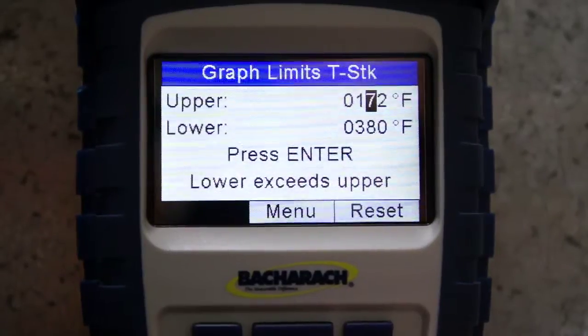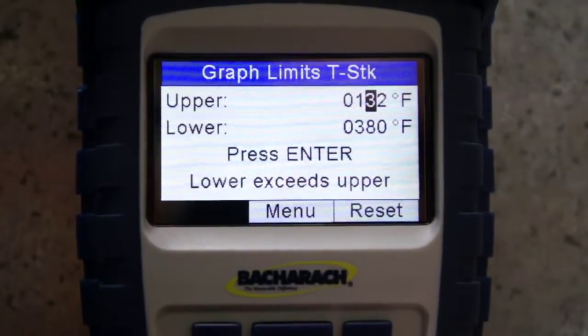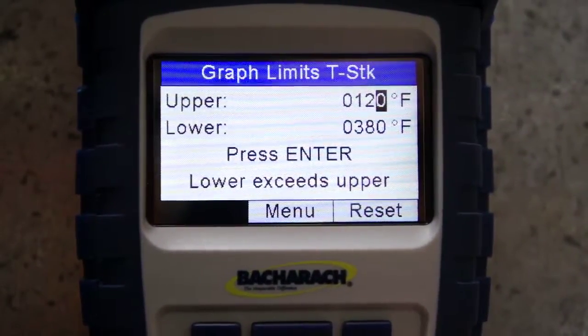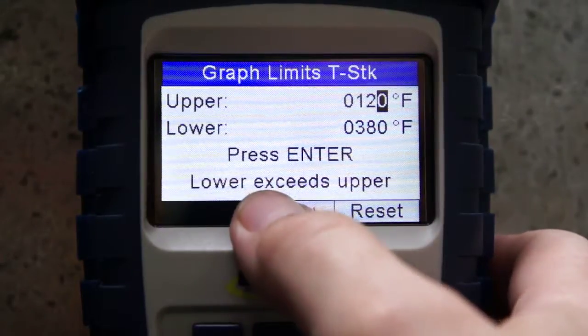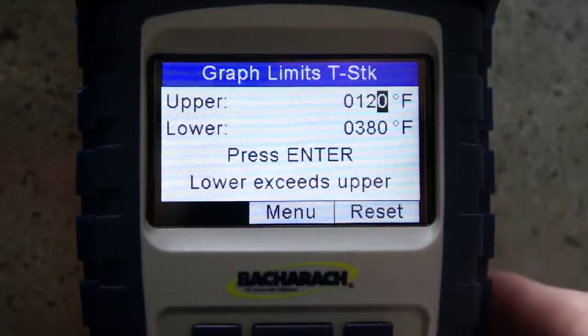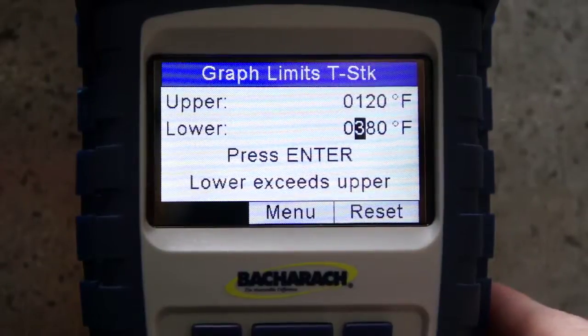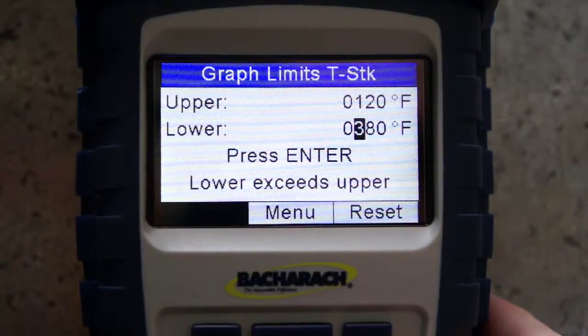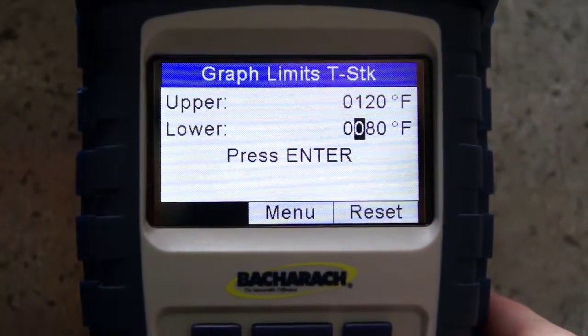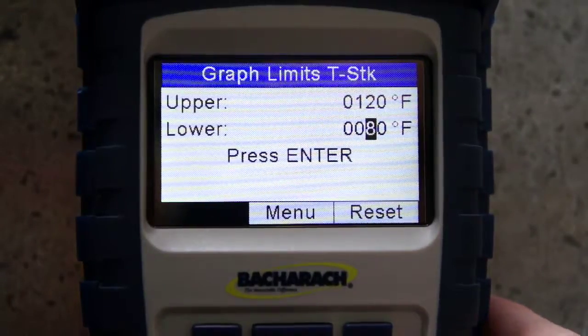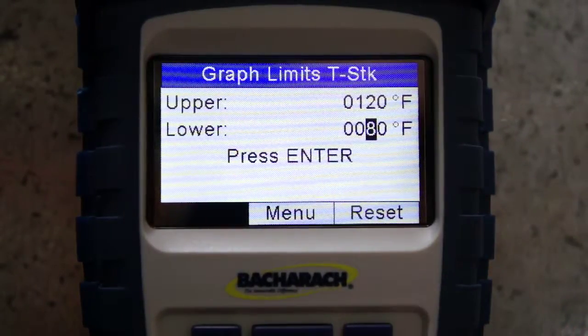Oops, we'll go back up to 1, 2, and 0. And you can see how I have a lower limit exceeds upper, so I definitely have to change the lower limit. My lower limit really should be my return air temperature and no lower than that. So I'm going to go to 80 degrees. And maybe I'll leave that, 80 is probably fine, and I'm going to hit enter.